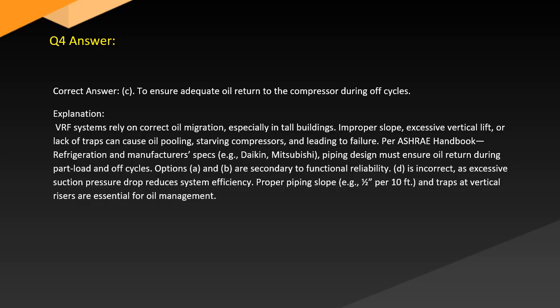Options A and B are secondary to functional reliability. D is incorrect, as excessive suction pressure drop reduces system efficiency. Proper piping slope, e.g., ½ inch per 10 feet, and traps at vertical risers are essential for oil management.